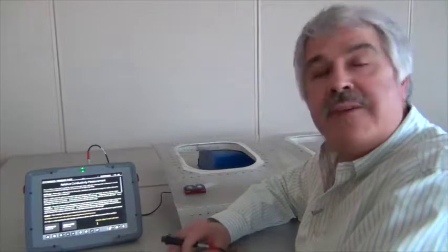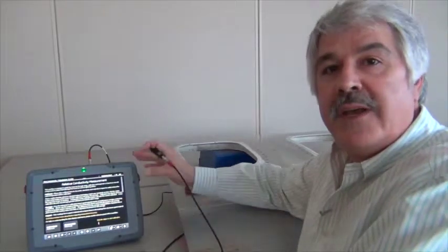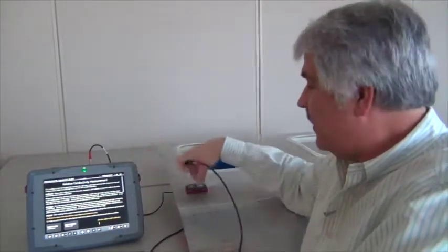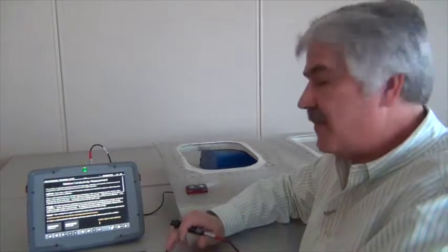Sometimes this is difficult in a maintenance hangar or other outdoor locations, but as much as possible, a little bit ahead of starting your test, take your instrument, your standards, your probe, start up your conductivity workflow, and allow everything to settle for a couple of minutes.